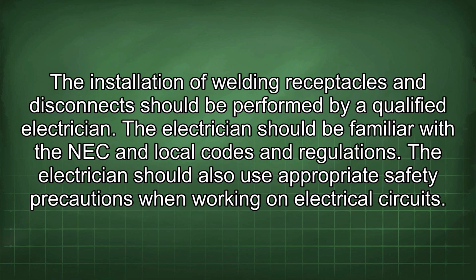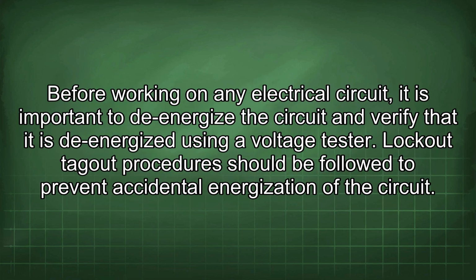The installation of welding receptacles and disconnects should be performed by a qualified electrician. The electrician should be familiar with the NEC and local codes and regulations. The electrician should also use appropriate safety precautions when working on electrical circuits. Before working on any electrical circuit, it is important to de-energize the circuit and verify that it is de-energized using a voltage tester. Lockout-tagout procedures should be followed to prevent accidental energization of the circuit.